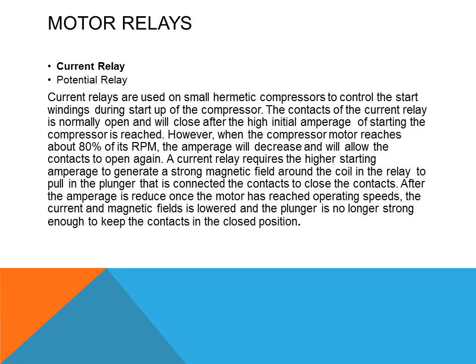The current relay is used on smaller hermetic compressors to control the start windings during startup. Its contacts are normally open and will close after the high initial starting amperage is reached. When the compressor motor reaches about 80% of its RPM, the amperage decreases and the contacts reopen. The current relay requires high starting amperage to generate a strong magnetic field in the coil to pull in the plunger and close the contacts. Once the motor reaches operating speed, the reduced current and magnetic field can no longer hold the contacts closed, so the relay opens.